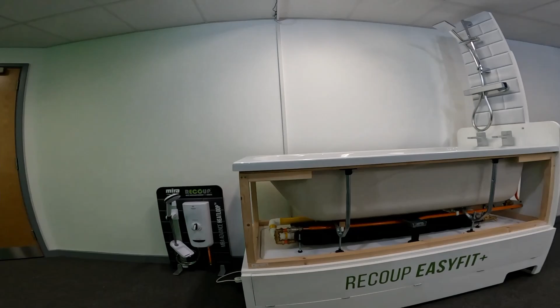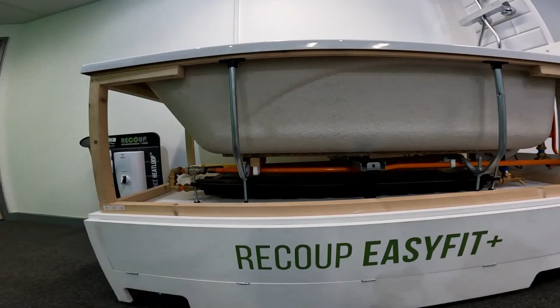Here we are, fitting nicely underneath the bath with no footprint taken up. The unit itself is just under 1200 mm in length and 386 mm in width, so it fits under a standard bath - in this case a 1700 by 7 - but we've had case studies where we can even get it under 1500 baths, albeit a bit of a squeeze. The total depth, once we've added the fall through the legs, takes it to about 95 to 105 mm, so well under the British standard 130 mm for a standard installation.